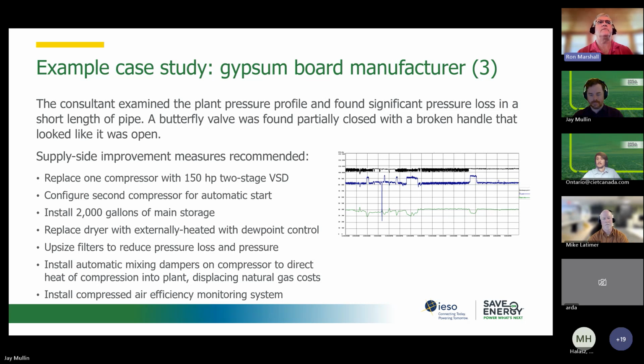Recommended they go with a variable speed drive compressor, put the other compressor in automatic start so it wasn't running all the time, installed significant storage to stabilize the system, put in a better dryer with a dew point controller, right? So that it wouldn't be purging that 180 CFM all the time. An externally heated dryer consumes half that and less with dew point control. It doesn't have to be purging all the time. We bumped up the filter size and used the heat of compression to heat the plant, right? And installed a permanent monitoring system on that system. Those are the recommendations, and that was actually done. Next slide.